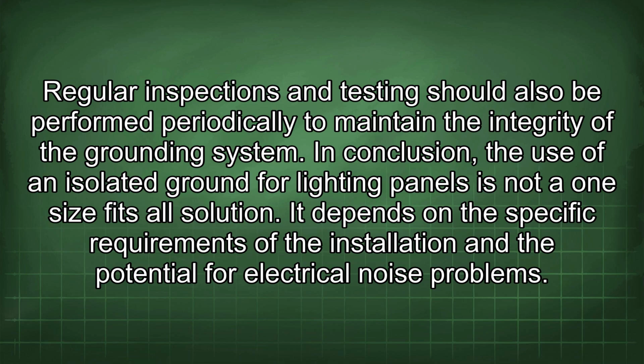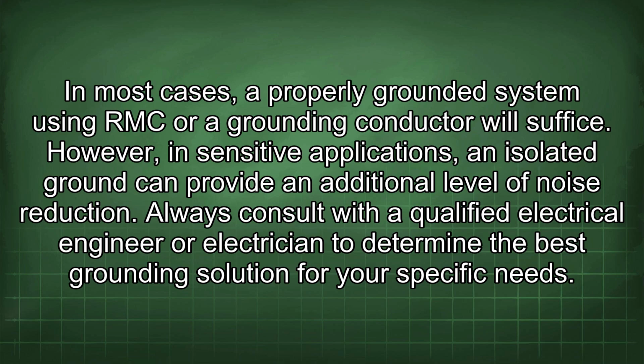It depends on the specific requirements of the installation and the potential for electrical noise problems. In most cases, a properly grounded system using RMC or a grounding conductor will suffice. However, in sensitive applications, an isolated ground can provide an additional level of noise reduction. Always consult with a qualified electrical engineer or electrician to determine the best grounding solution for your specific needs.